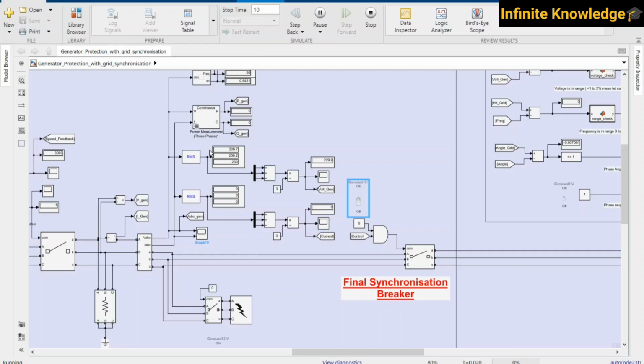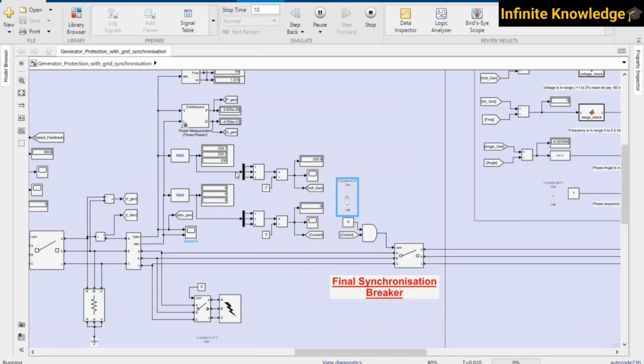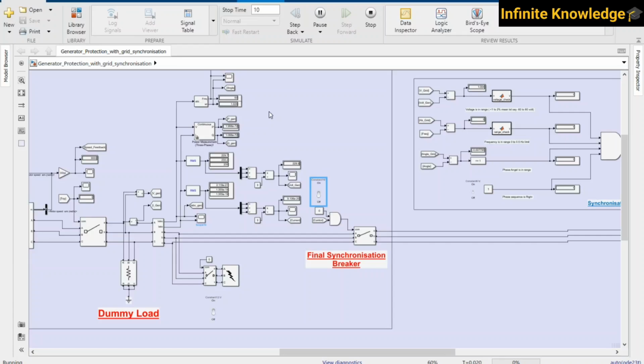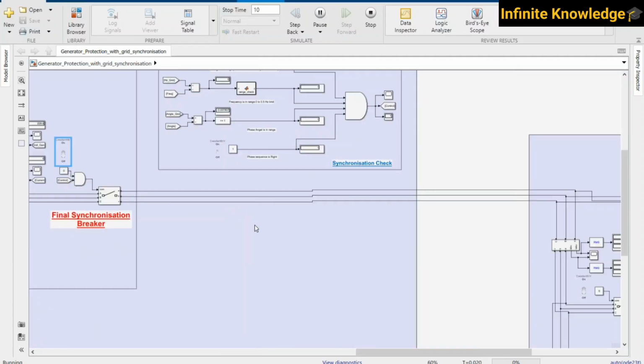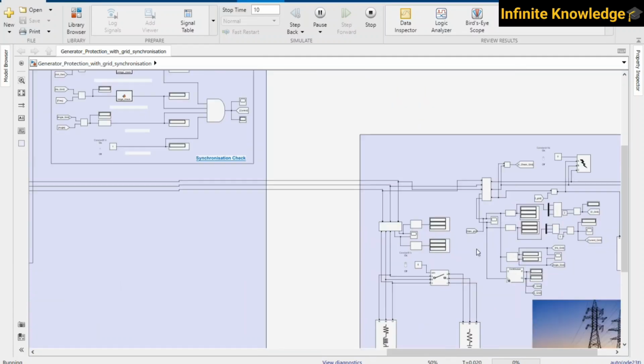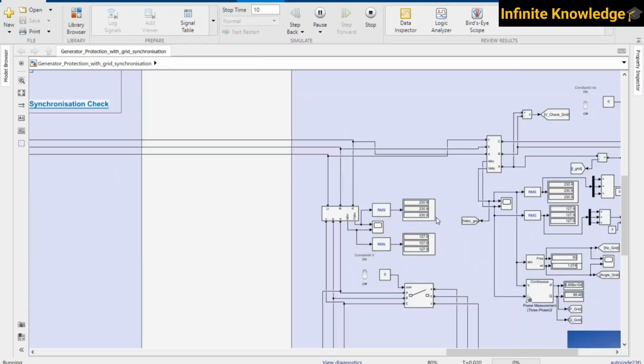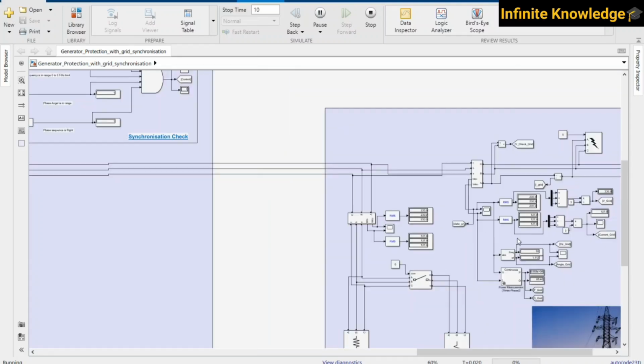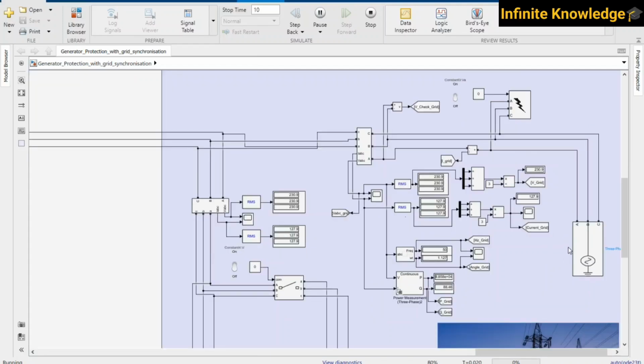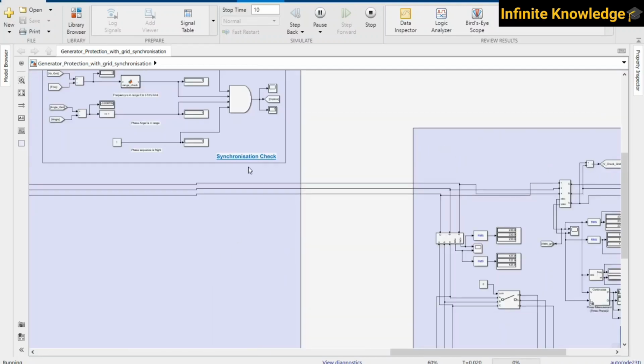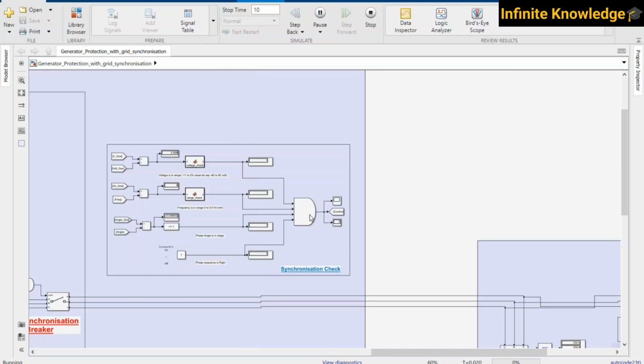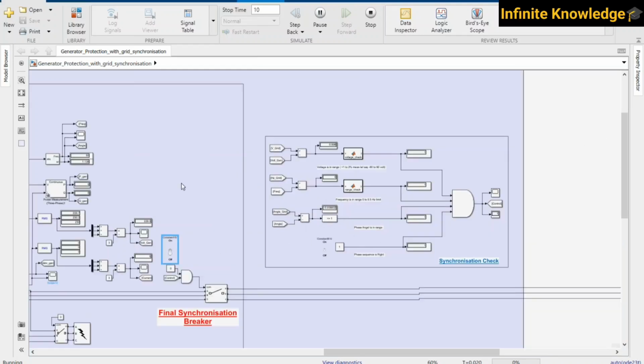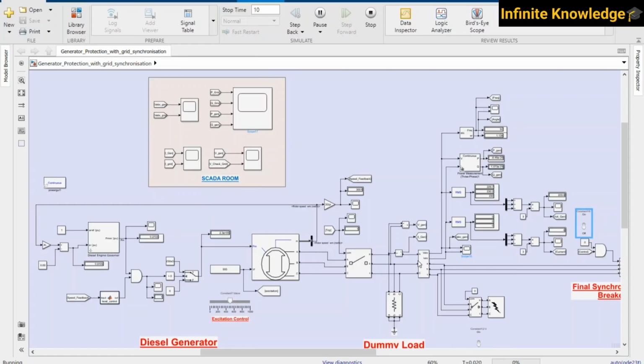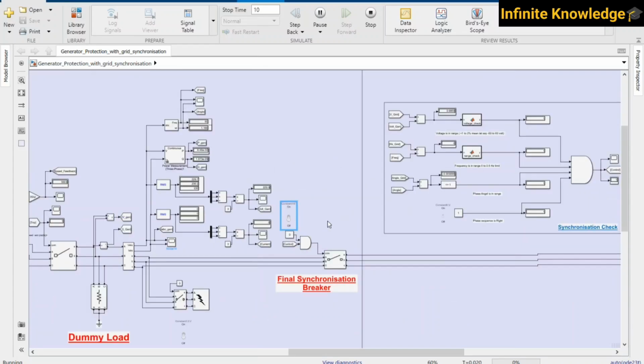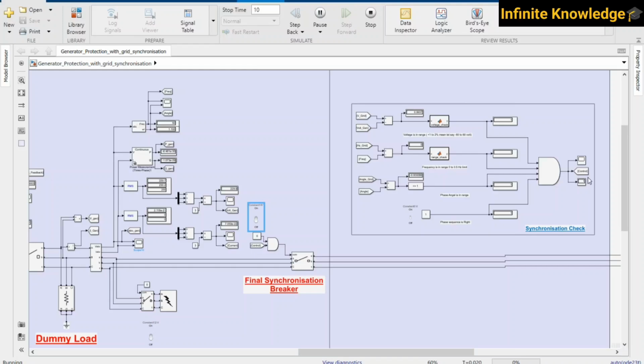Okay, so right now I can say we have very near voltage to the grid supply, so I can start the, or I can synchronize with the grid. So you can see this is the ampere that is taken by the load, and this is the ampere that is fed by the grid. Okay, and we need to check all the conditions. If everything is 1, then it is okay, and if it is 1, we can just press the generator synchronization. Okay, this is 1, and if it is 1, then I can press this switch.